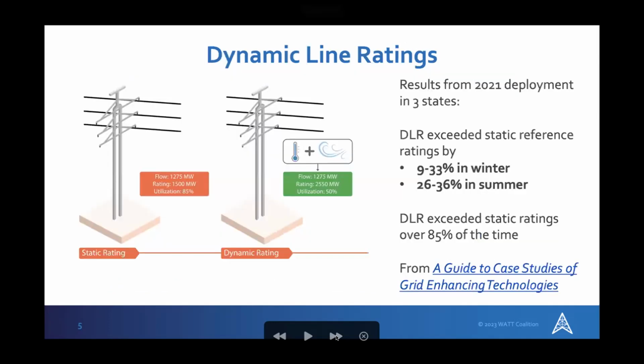Dynamic line ratings are our third grid enhancing technology. These are sensors that go on or near the transmission line or towers, and they measure the capacity of the lines. Most often in the United States, lines have a static rating, maybe a seasonal rating, and that assumes the worst case scenario: it's hot, there's not much wind, and the power is heating the line, with ambient conditions not really cooling it. With dynamic line ratings, you can tell whether the line is being cooled by ambient conditions.